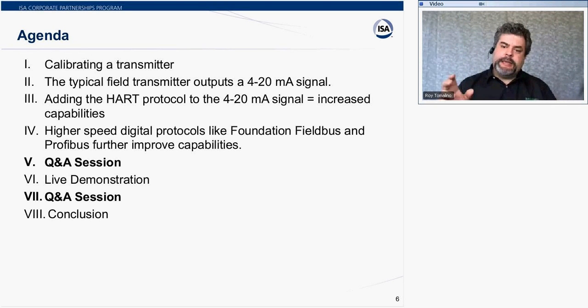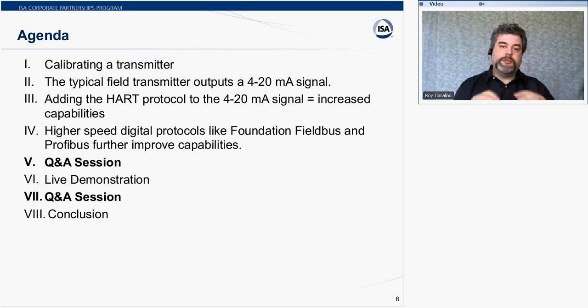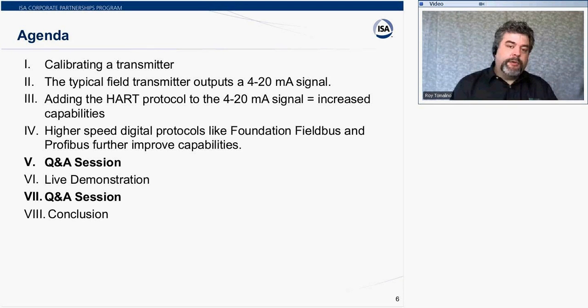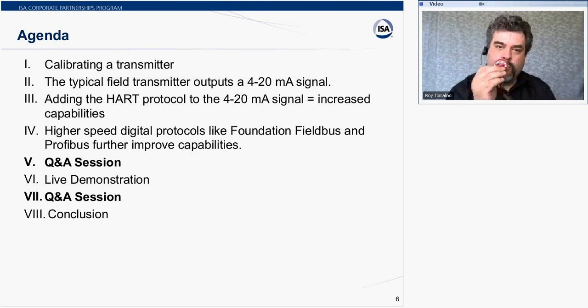Welcome everybody to our discussion on calibrating smart transmitters. I'll be doing some live demonstrations with video, and I'll also have a remote controller on the screen to help you see what's going on. You can double-click on the video itself to either change the size, make it go larger or smaller. The first thing I want to show is calibrating a fieldbus transmitter. The first thing we'll do is verify the transmitter and hook it up. If I have a four-wire temperature transmitter — this happens to be a hockey puck — we've got different hockey puck options.